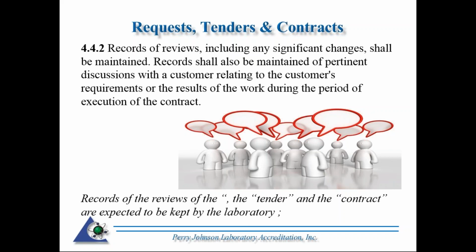If I'm doing an assessment, I just typically would point blank when I get to 4.4.2, ask where these records of pertinent discussions would be maintained. It could be maintained electronically. It could be maintained within hard files that are being maintained in file cabinets within the laboratory. So we're looking for the records of the reviews of the tenders and the contract, and they are expected to be kept within the confines of the laboratory.